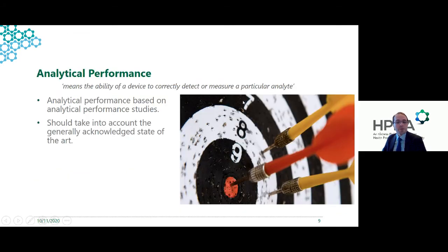For analytical performance, this is the link between the device and the analyte in question. Most of the time, analytical performance is based on performance studies. This is where you actually go out and measure how good your device is at detecting specific parameters of the analyte - limit of detection, interferences, accuracy, reproducibility, those kinds of parameters. And it should take into account the generally acknowledged state of the art.